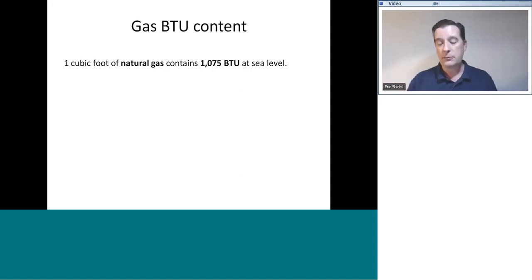In general, the amount of heat energy contained in a cubic foot of natural gas ranges somewhere between 950 BTU per cubic foot and 1100 BTU per cubic foot. Depending on where you are, depending on your natural gas provider and the unique circumstances of their delivery infrastructure system, your gas may have somewhat more or somewhat less BTU per cubic foot. Also, based on your altitude, this will also change. Remember, this is at sea level.